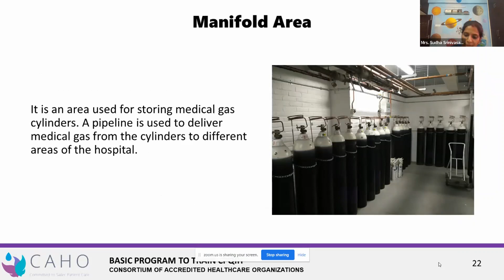Right, and the construction of the medical gas installations should be as per the norms. Here we are talking about the manifold area. How should these cylinders be placed? There should be a segregation of full and empty cylinders, and labeling of these cylinders is very, very important. Before that, appropriate signages on entry restriction. Anybody should not be able to walk inside the department and just turn off the valve. Probably that would cut down the supply of the medical gas to the various areas, which could even be OT and critical care areas like ICU. So which could be disastrous for a hospital. So entry restriction is very, very important.